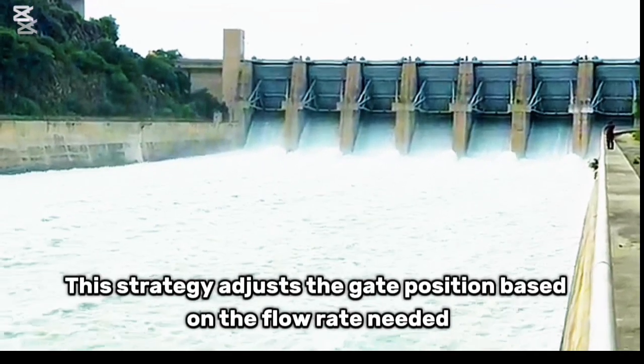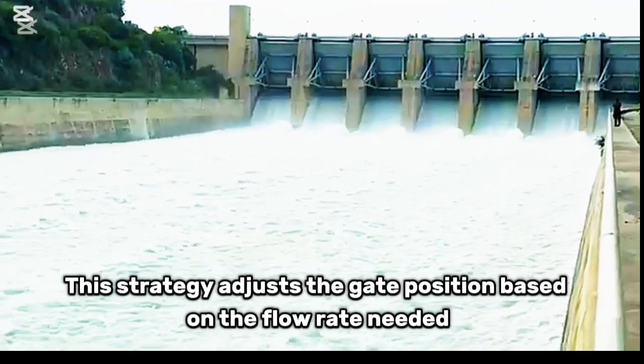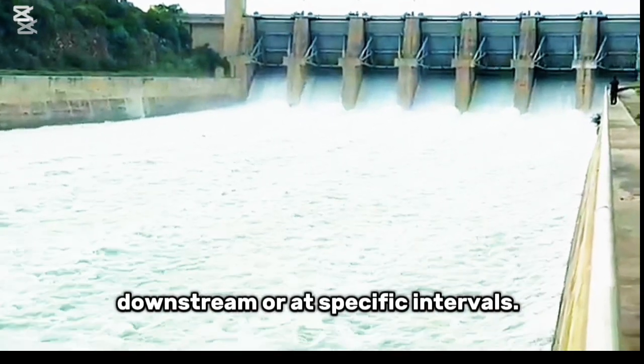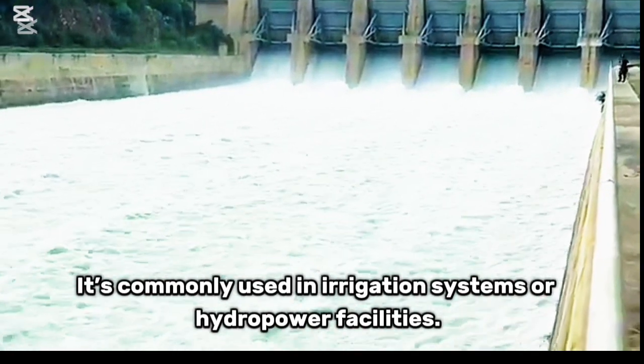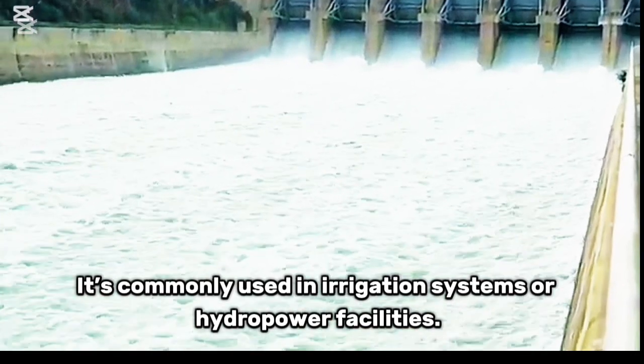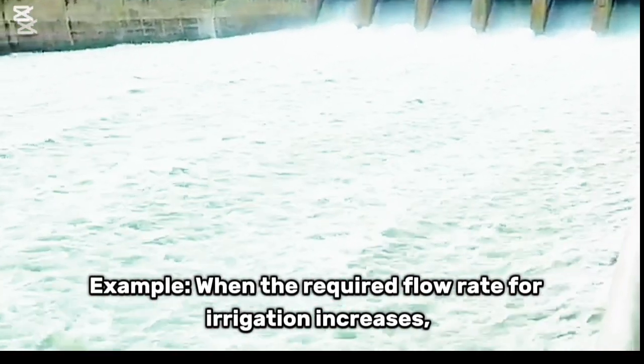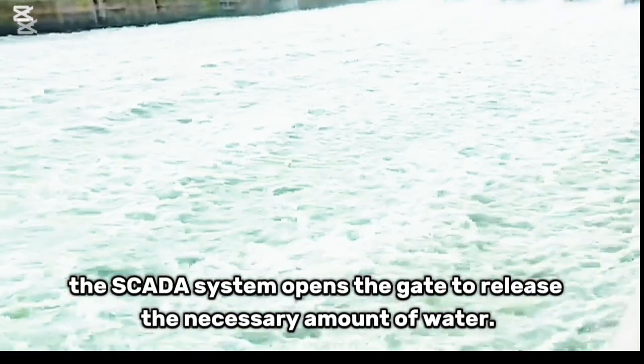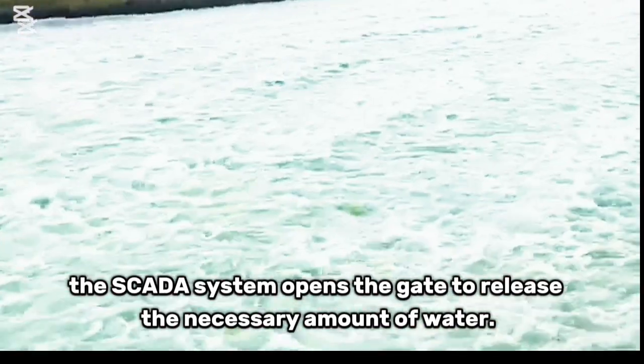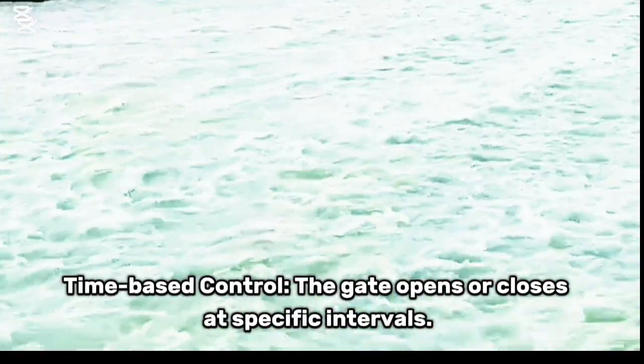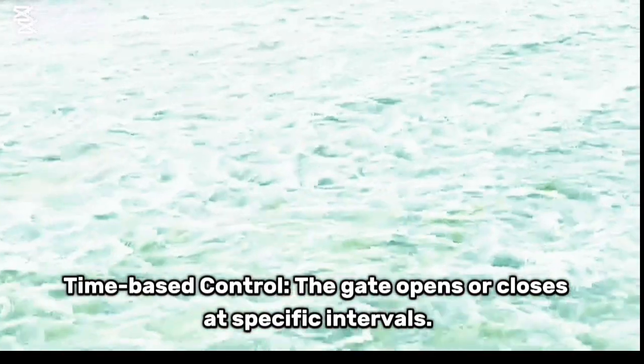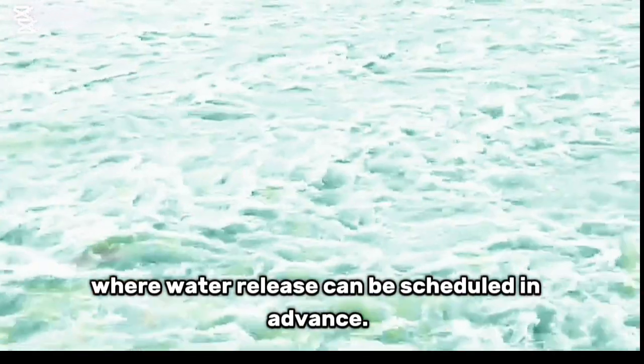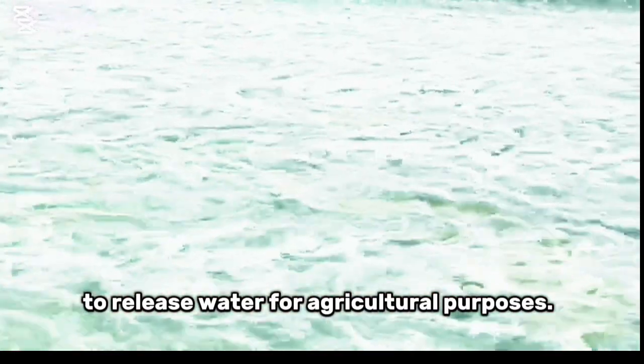Flow-based control. This strategy adjusts the gate position based on the flow rate needed downstream or at specific intervals. It's commonly used in irrigation systems or hydropower facilities. Example: when the required flow rate for irrigation increases, the SCADA system opens the gate to release the necessary amount of water. Time-based control. The gate opens or closes at specific intervals. This is often used for non-emergency applications, where water release can be scheduled in advance. Example: a gate might open every day at 6 a.m. to release water for agricultural purposes.